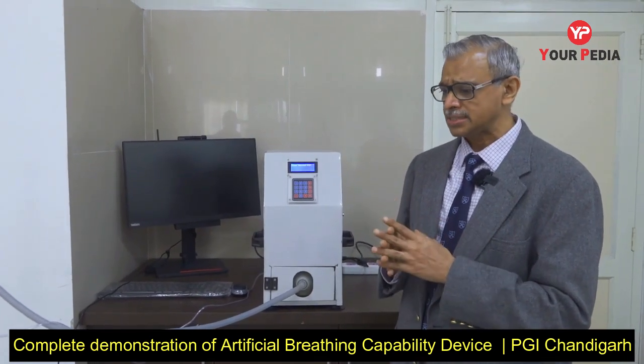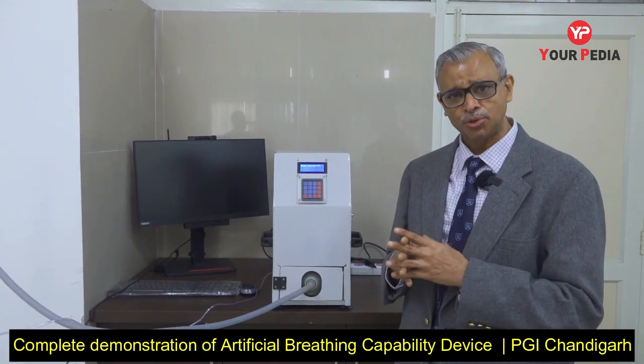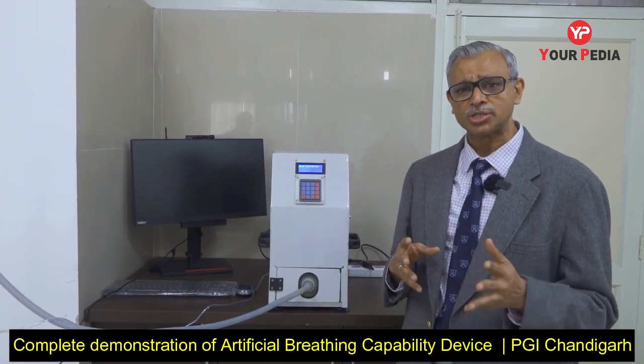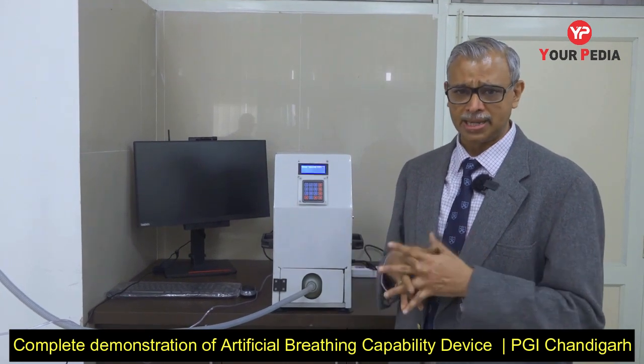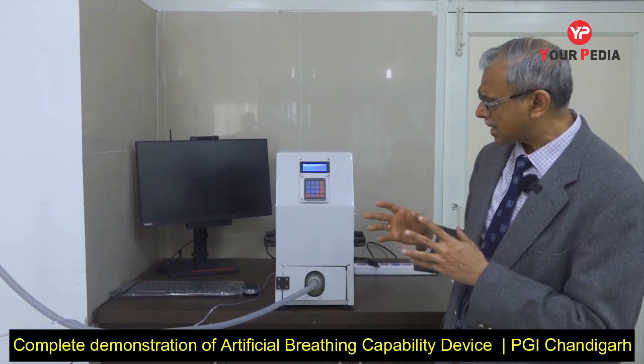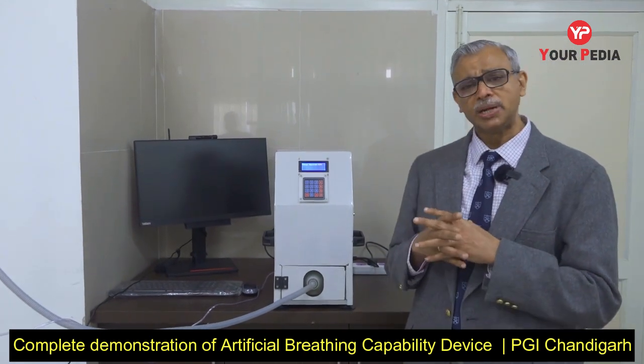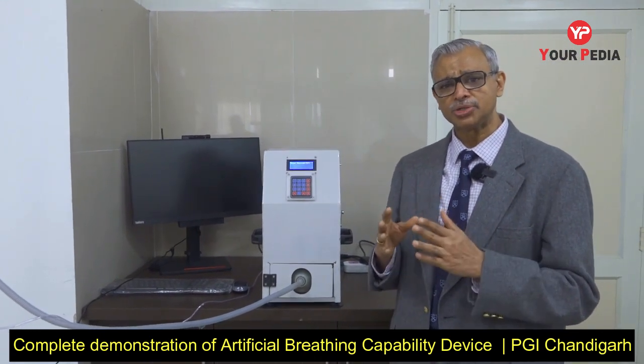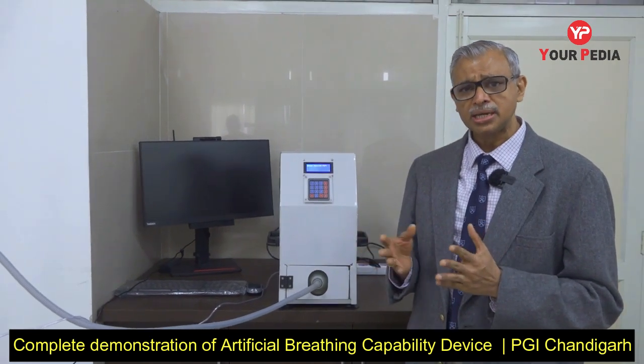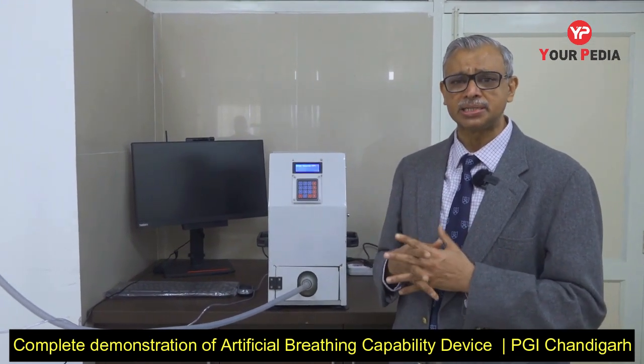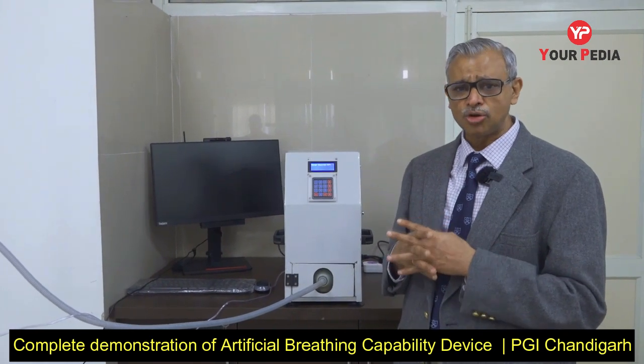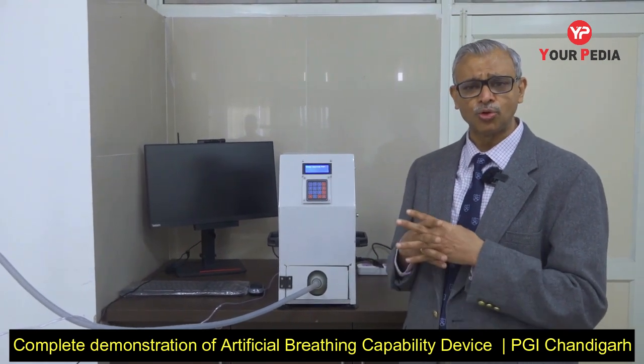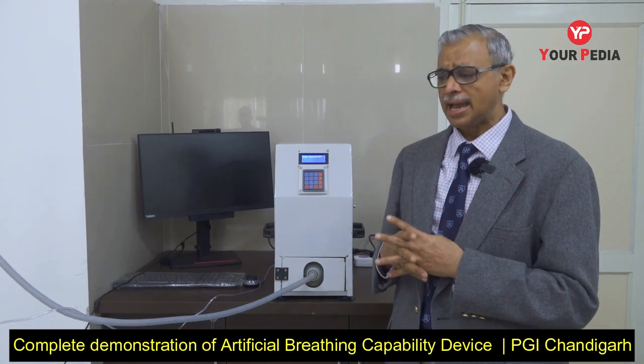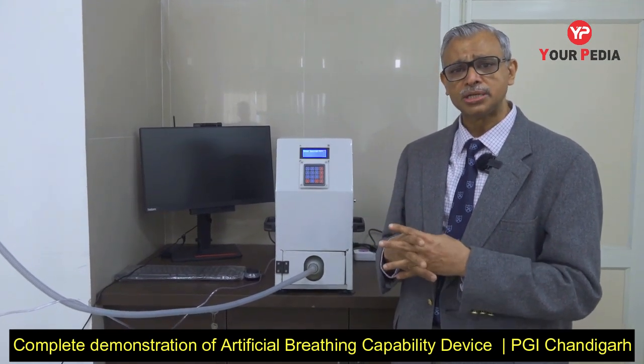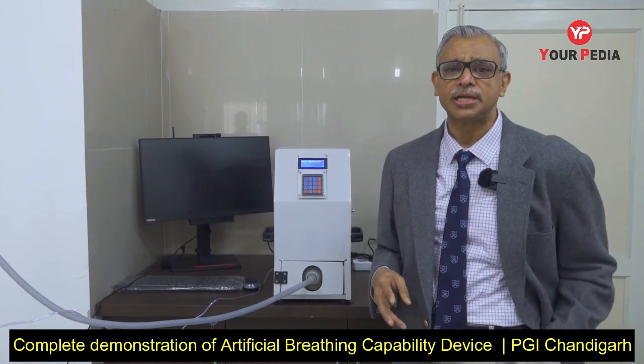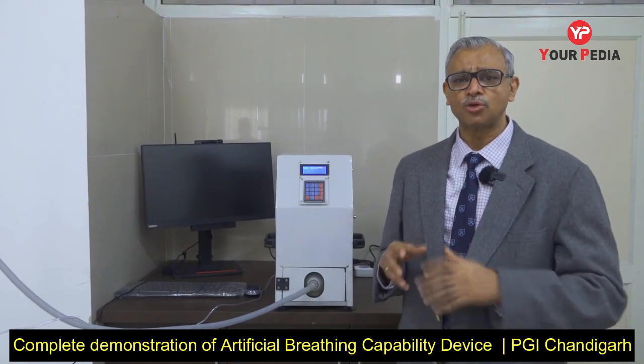We are also able to set the inspiratory to expiratory time ratio in any fraction ranging from 1:1 to 1:4, just like a mechanical ventilator. This device has a lot of safety features. We've got built-in alarms. For any pressure which goes outside the controlled range, plus or minus 10%, there will be a beep. If there is excessive volume, there will be a beep. If the flows go out of range, there will be a beep. And there are different kinds of alarms for tube blockage, tube disconnection, endotracheal tube blockage, and also for what is called a cough alert.